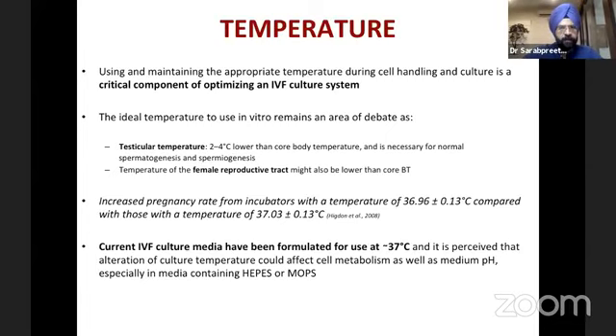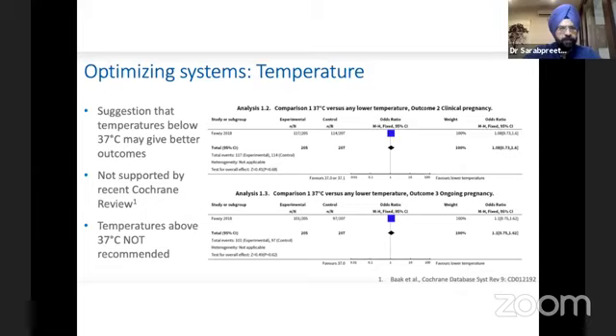Again, there was a lot of debate about the ideal temperature to use in vitro, as the testicular temperature is 2 to 4 degrees lower, and the temperature of the female genital tract is also lower than core body temperature. It was shown by Higdon et al. that a temperature of 36.9 degrees gave better results compared to a temperature of 37 degrees. But recently, it has been shown that the current IVF media is designed for use at 37 degrees. And if you look at this Cochrane review, it shows that temperatures below 37 degrees may give better outcomes, but they're not supported by a Cochrane review. And it is recommended that you use the media at 37 degrees only. So don't fiddle with your incubator temperatures, rather ensure that they are set at 37 degrees.